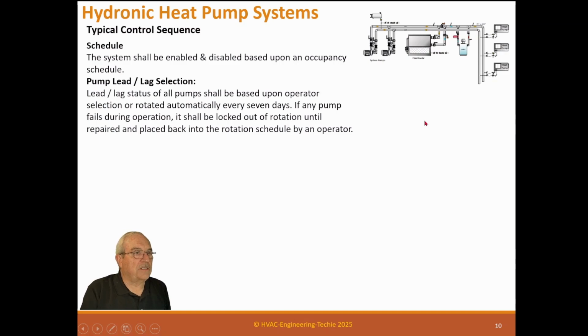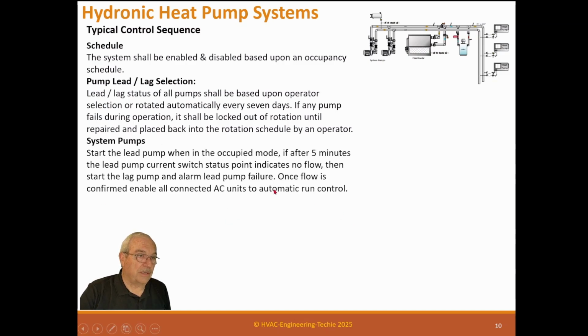Pump lead/lag status of all pumps should be based upon operator selection or rotated automatically every 7 days. If any pump fails during operation, it should be locked out of rotation until repaired and placed back into rotation by an operator. It's really important that someone fix a pump before we try to run it again.